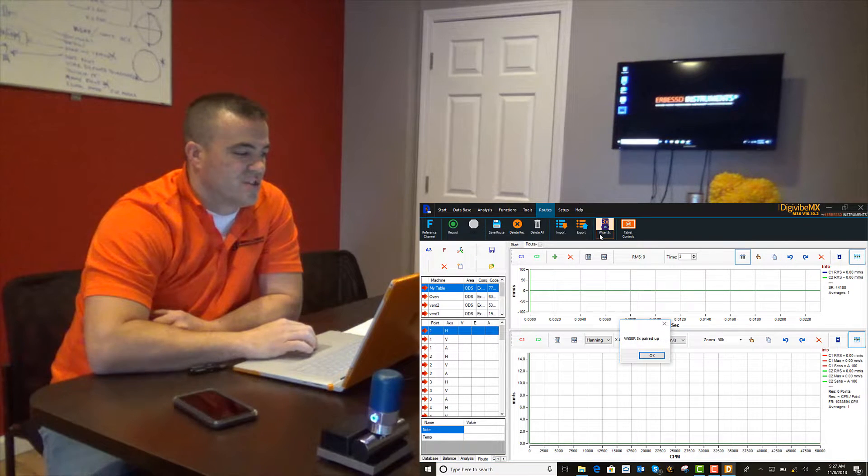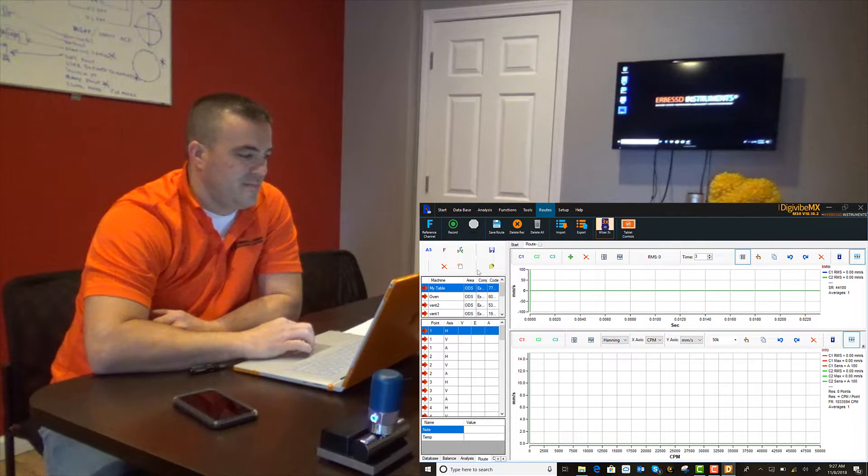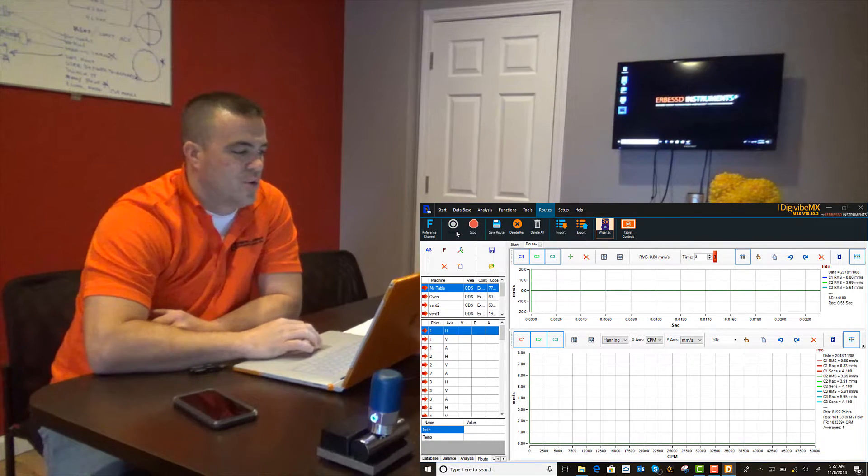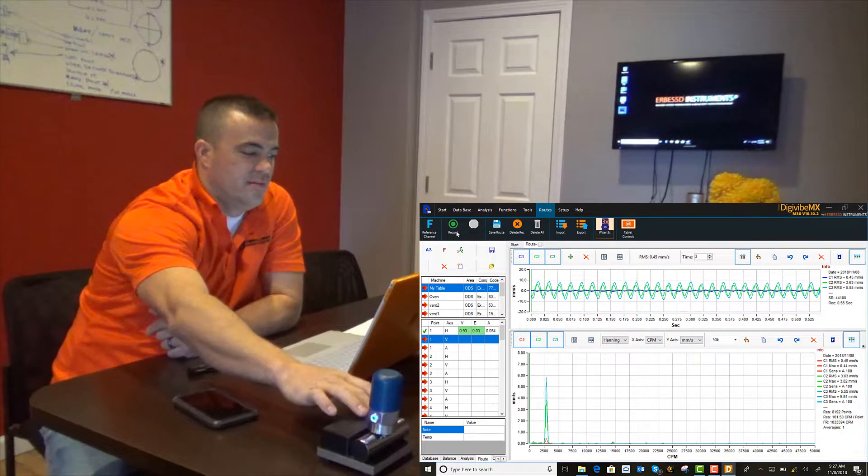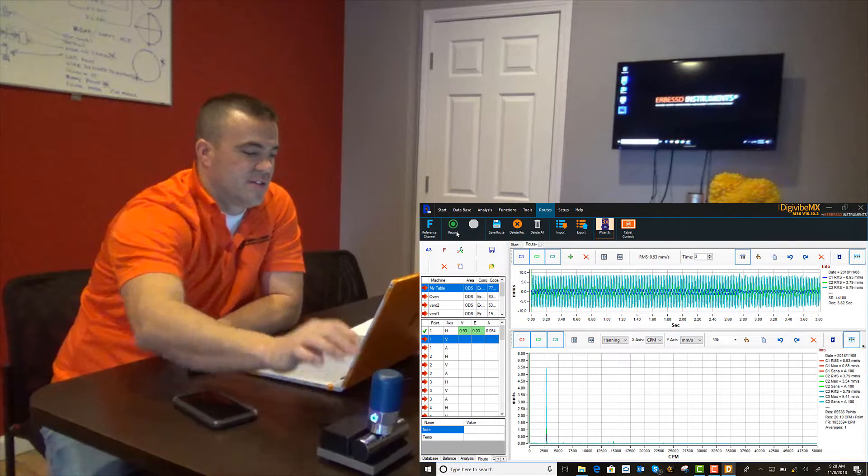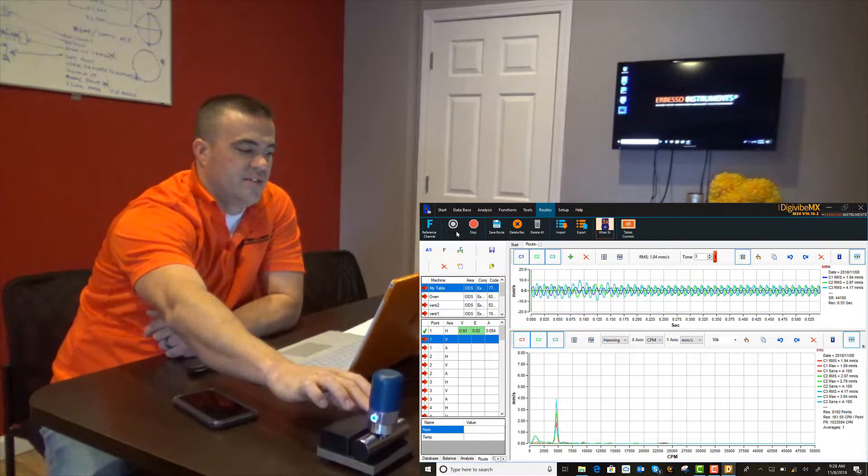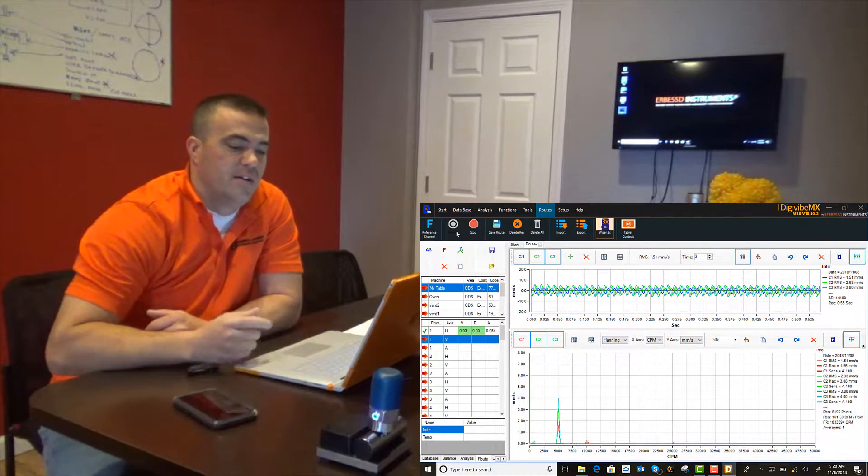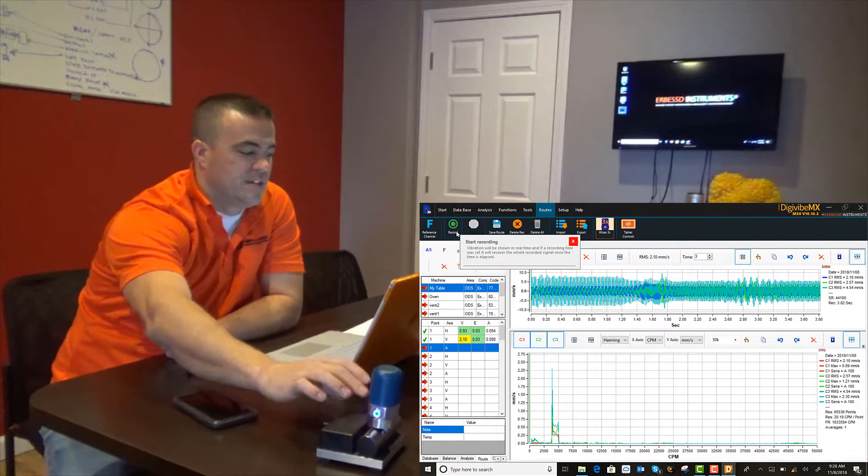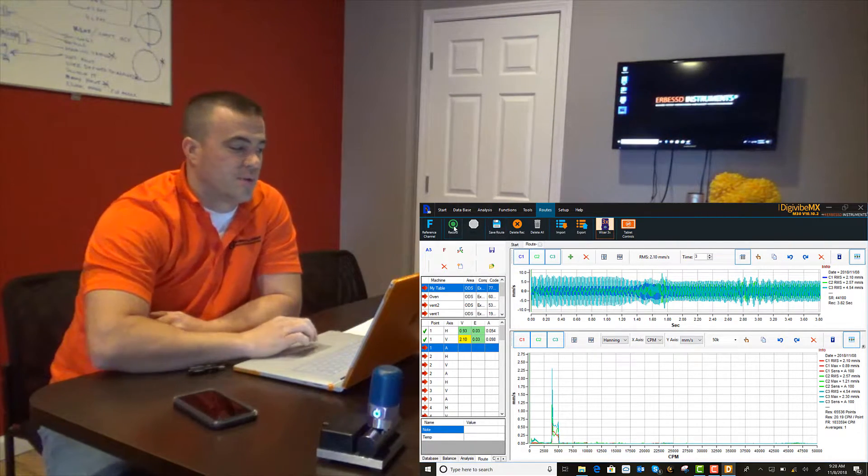Once you have your route selected, you can add additional channels. Hit the 3X button for Wiser 3X. You'll see that we're paired up. You've got all three channels. We can go ahead and hit record. And again, three independent channels of tri-axial data live streamed by Wi-Fi from the Wiser 3X to our Windows tablet running DigiVib MX software.